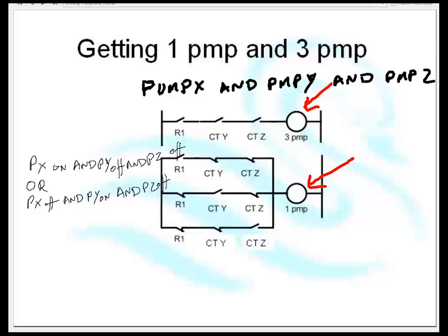Now there's two important words that just popped up there. Firstly, I've got these ANDs. The ANDs are telling me that I'm wiring in series. So here, I'm wiring in series. The second important word is this OR. The OR tells me that all of the stuff on the top line is in parallel to all of the stuff in the bottom line. OR means series switches in parallel, and AND means switches in series. If you can write it out in English, find the ANDs, find the ORs, you can wire it.